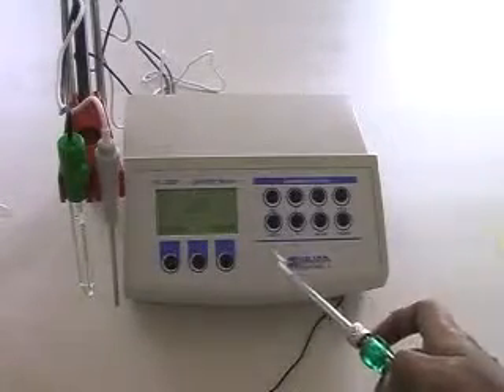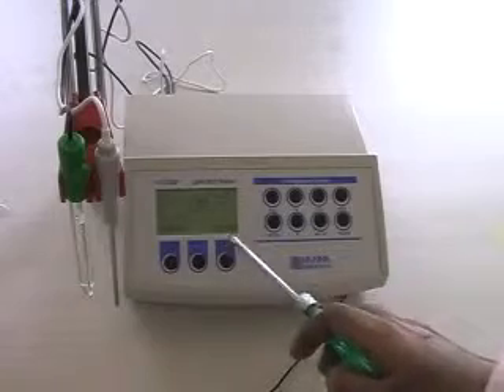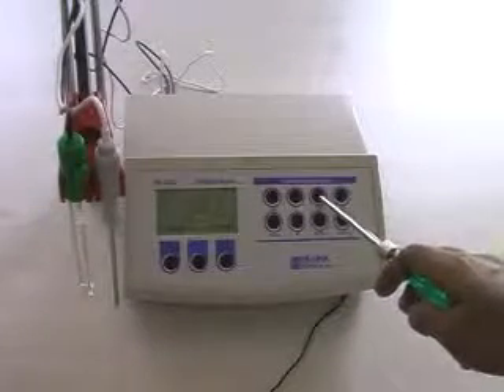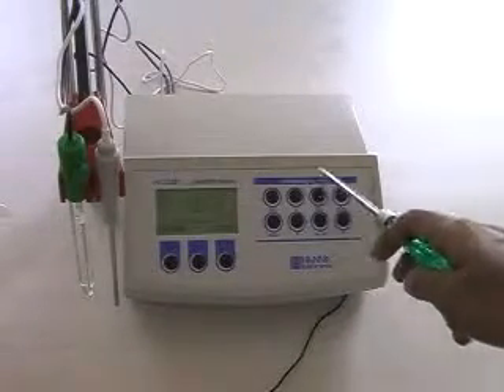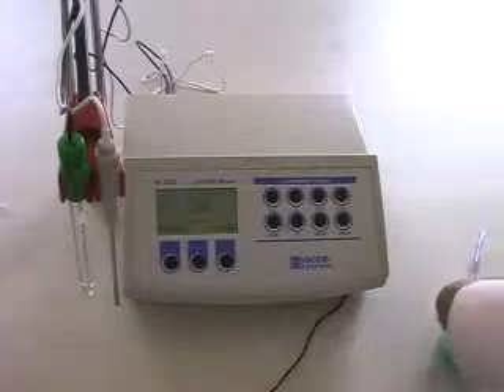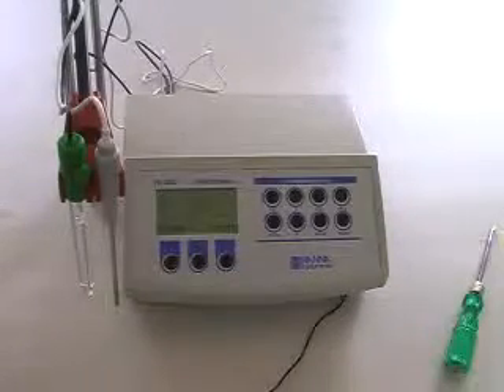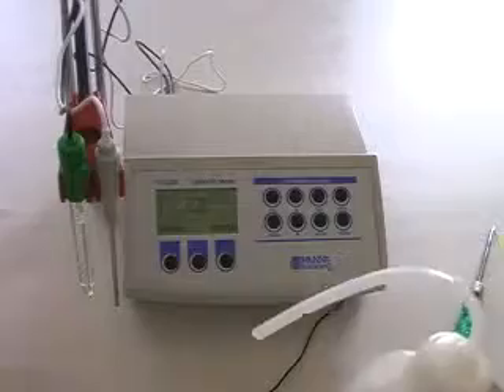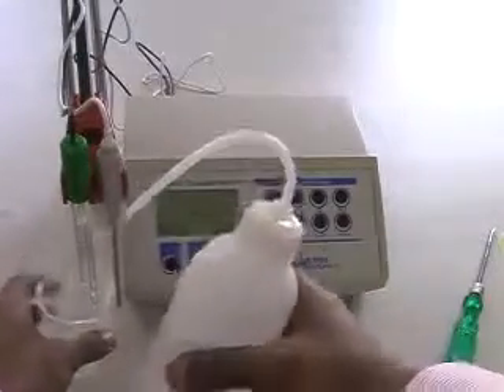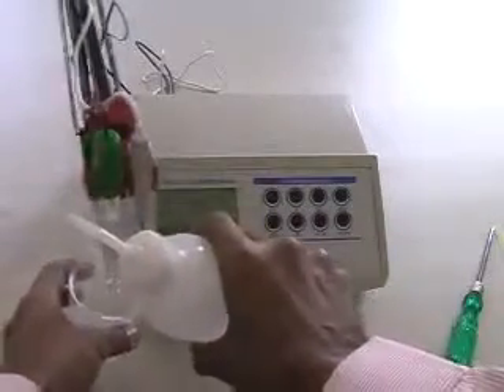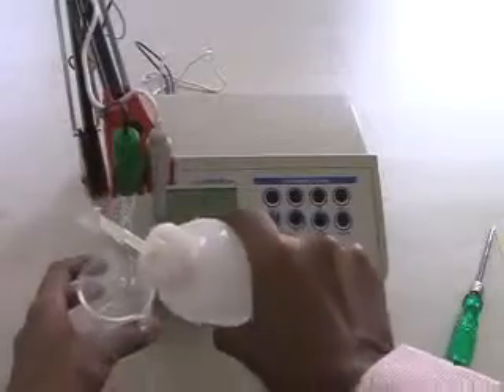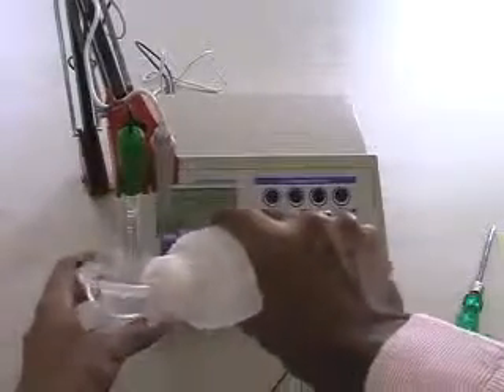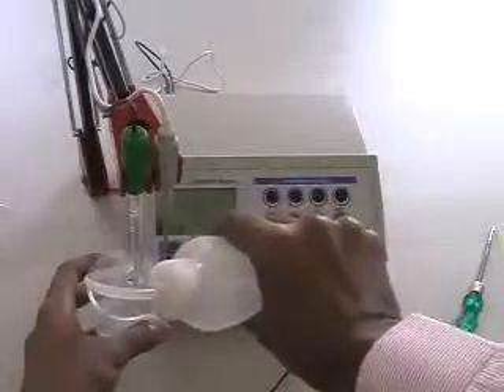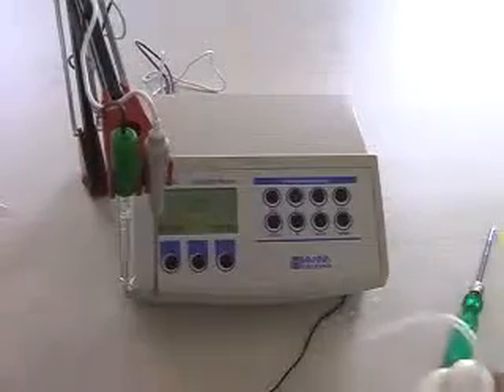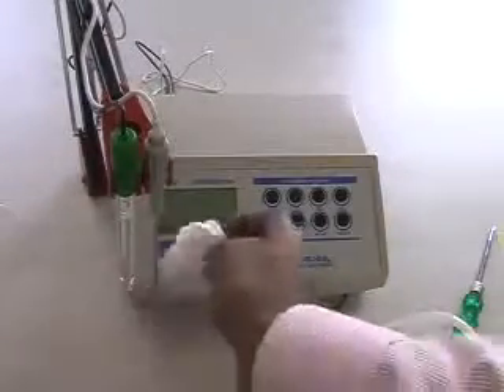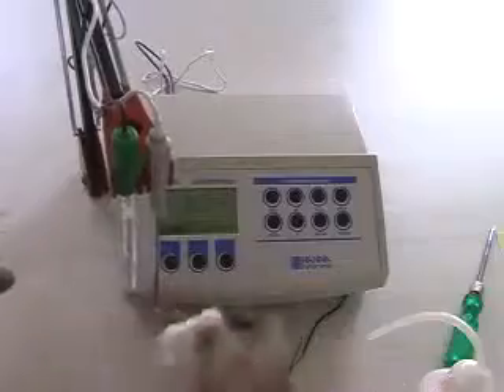For calibration, this is the calibration button. You have to press this CAL button to calibrate your meter. Now we will learn how to calibrate your meter. Before calibrating, just clean your electrode with a small amount of distilled water. Make sure that there is no contamination. Then just clean your electrode with a soft tissue paper.